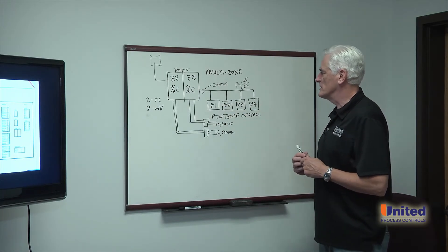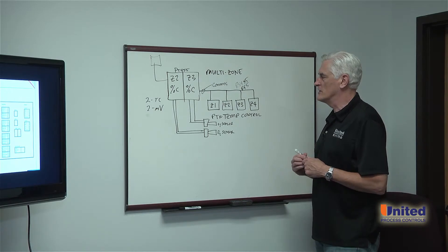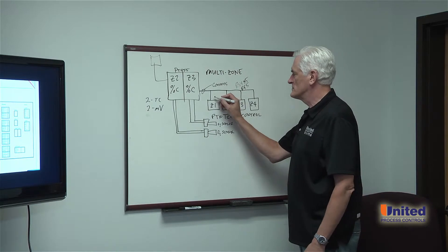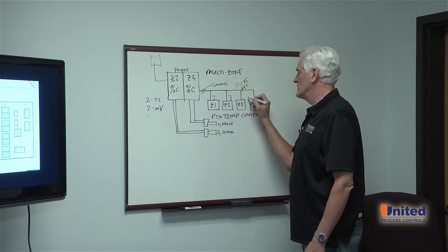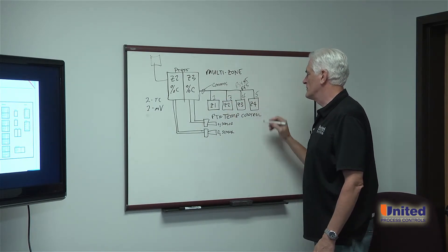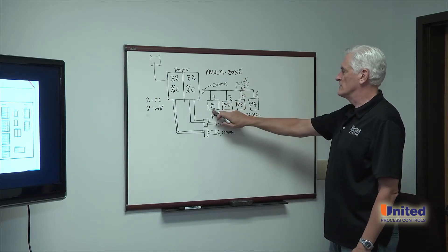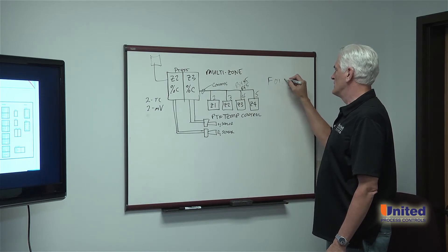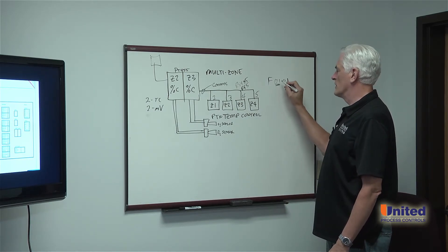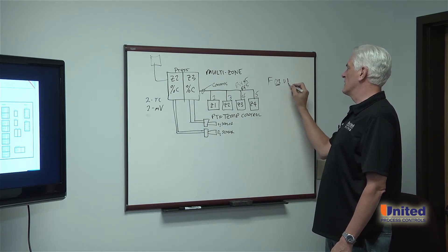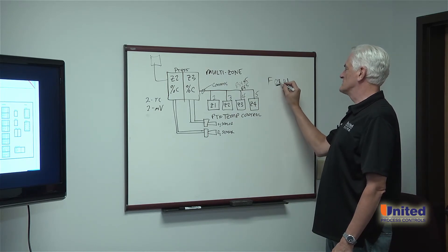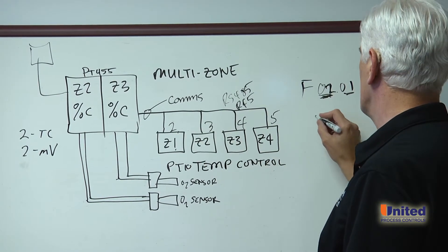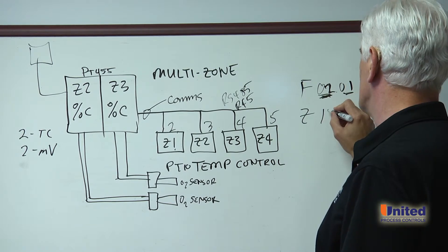For example, if there's a recipe for a setup, I can manage each one of these set points by using the flag and Z opcode in the recipe. If I configure these as flag two, three, four, and five, and I wanted to change the set point on zone one controller, I would issue flag zero two, zero one to turn the flag on.